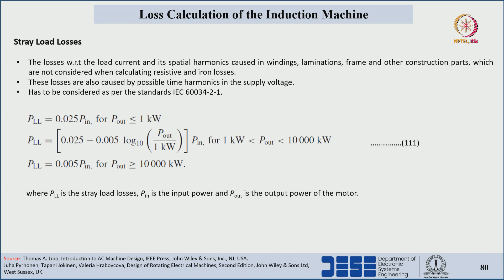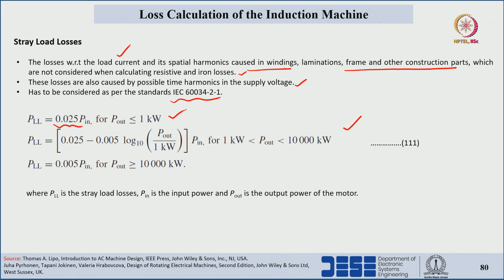Stray load losses are the losses not accounted for by stator copper losses, core losses, and mechanical losses. They include losses due to load currents and their spatial harmonics caused in windings, laminations, frame, and other constructional parts. These losses are also caused by time harmonics from the supply voltage and must be considered per IEC standards. For machines rated below 1 kW, stray load losses are 2.5% of input power.